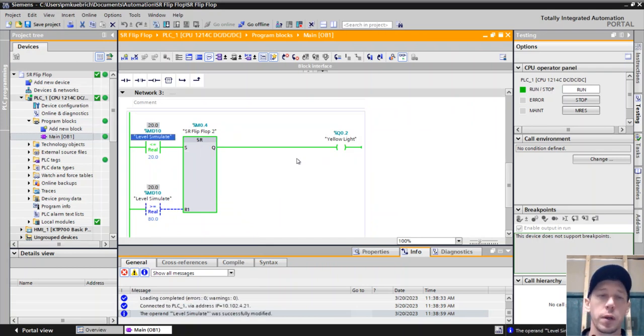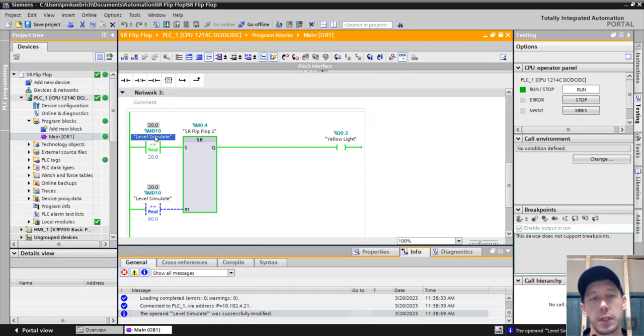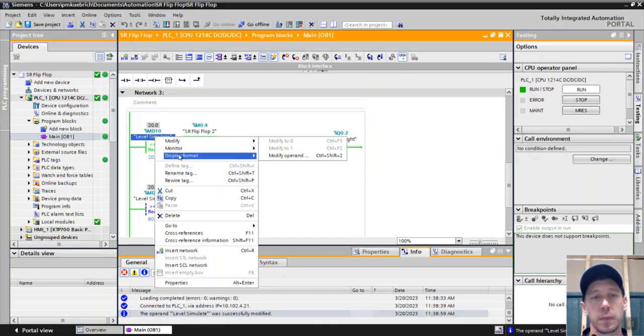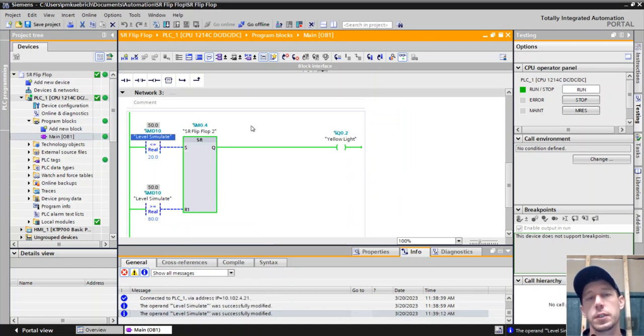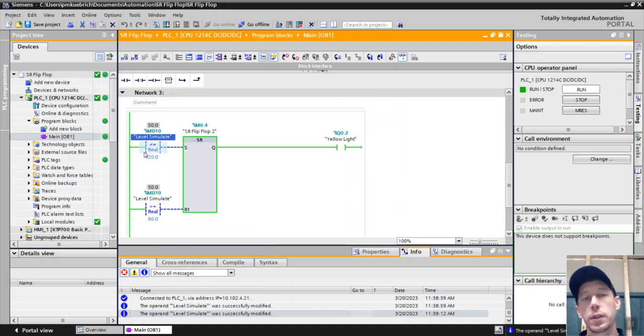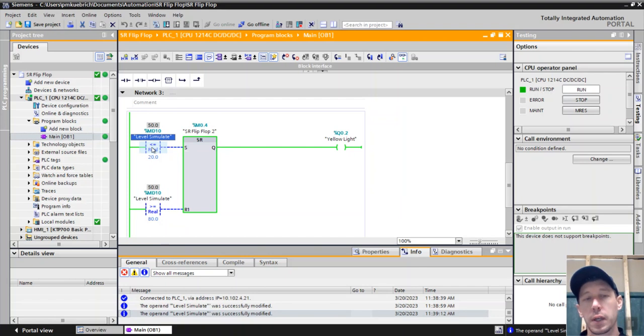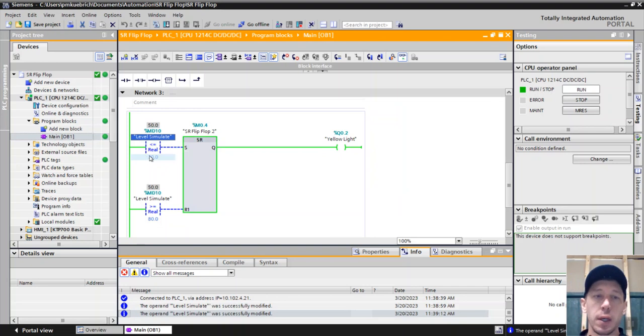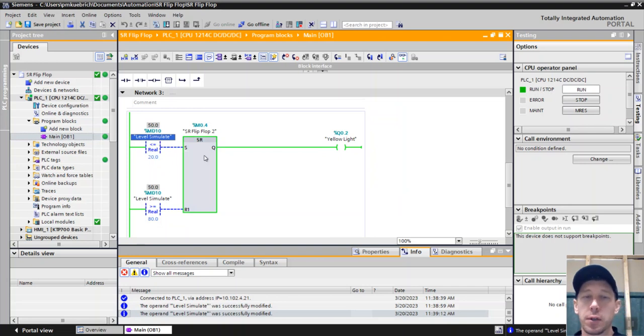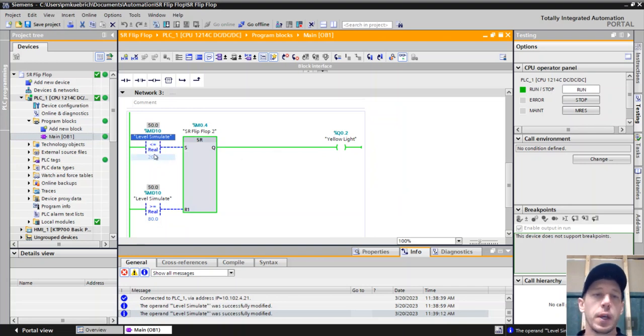Now here's where a little bit of the difference starts to come in. If I go up to fifty percent, the tank is still filling, the pump is still running. Notice this bit goes false then because fifty is not less than twenty, but since we have it into a flip-flop it's set and it stays on. So fifty, it's still on, still filling up, the tank is still filling up.